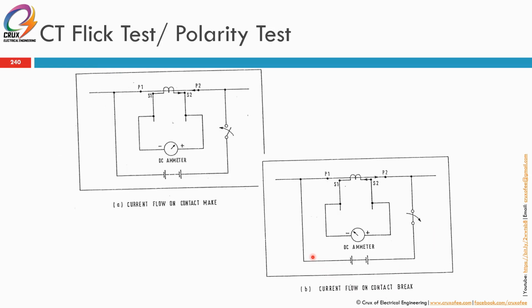Alright, so let's see for the CT test how to check the polarity. One of the easiest tests to check the polarity is the CT flick test. You connect a battery to the primary circuit with a switch, and you connect a meter to the secondary circuit. This meter will be a meter with a positive and negative scale.